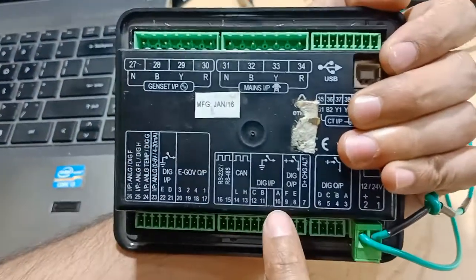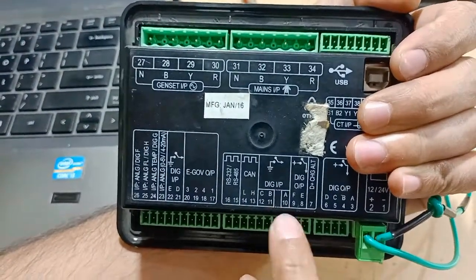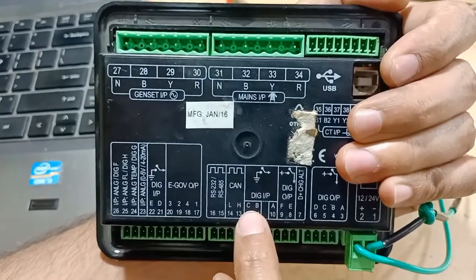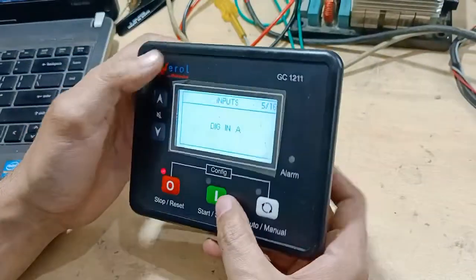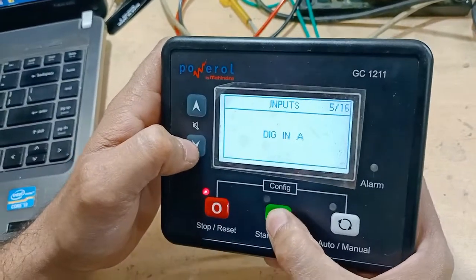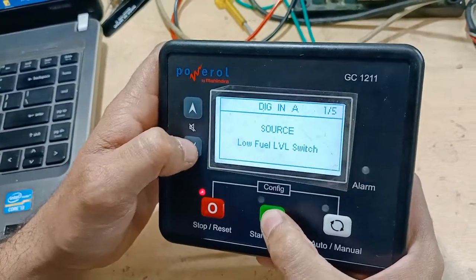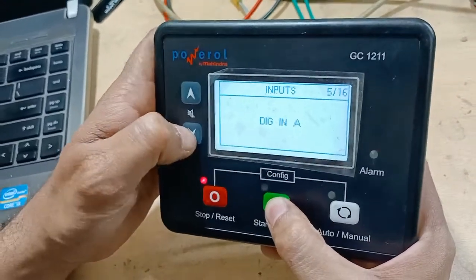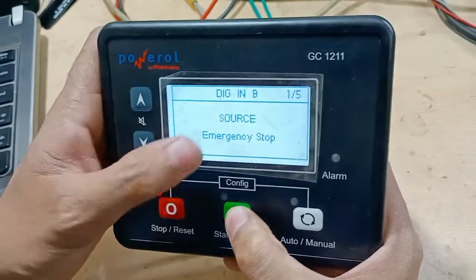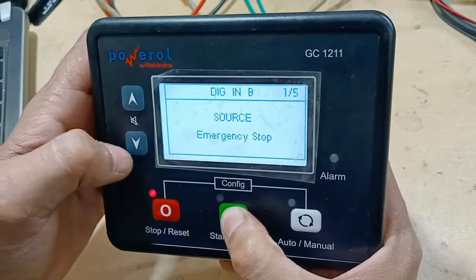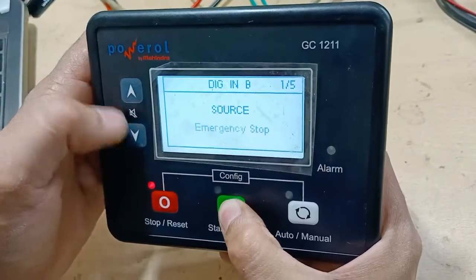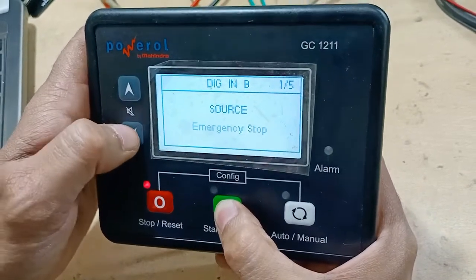Under digital inputs, the input labels A, B, C, D, E are written on the back side of the controller. At input A, you can configure it — by default it is set to low fuel level switch. At input B, it is emergency stop.